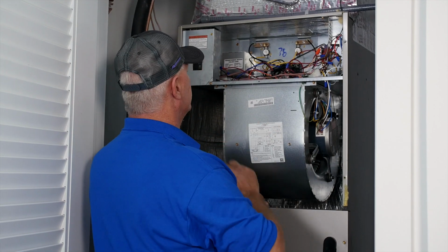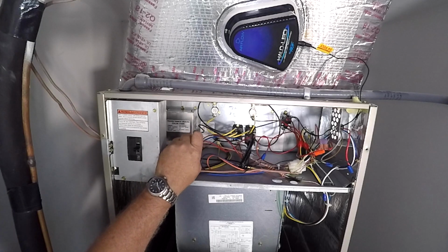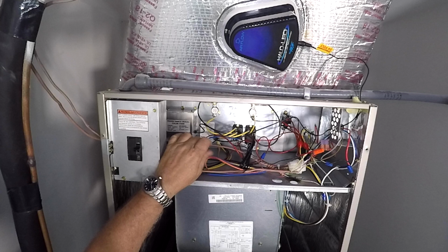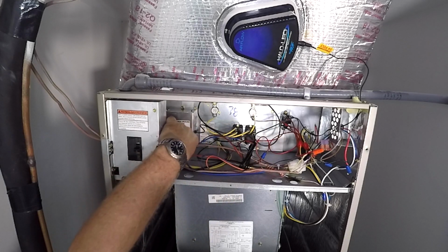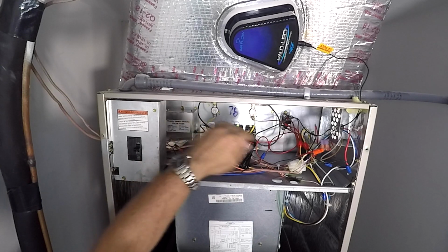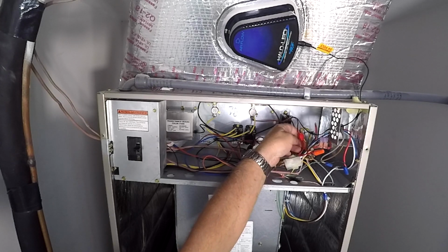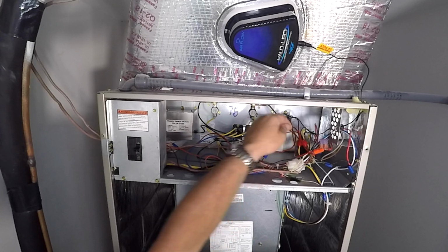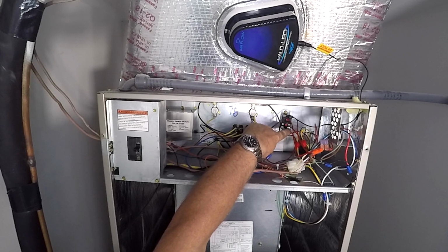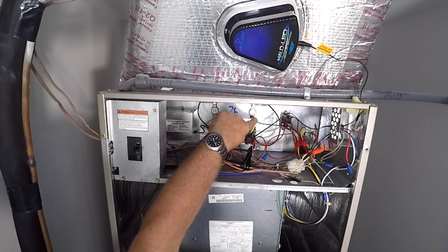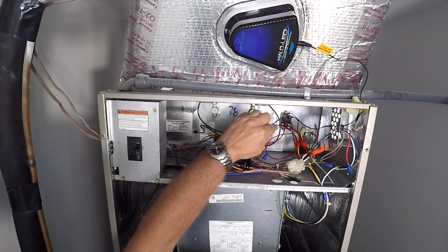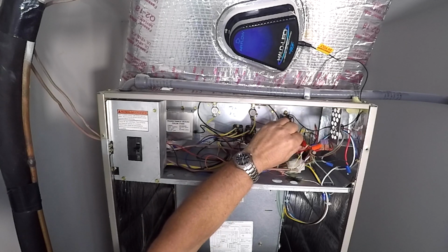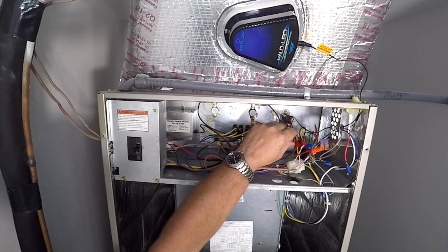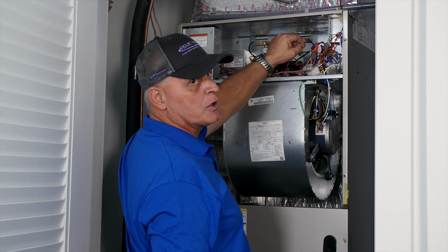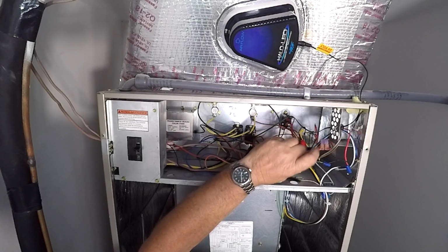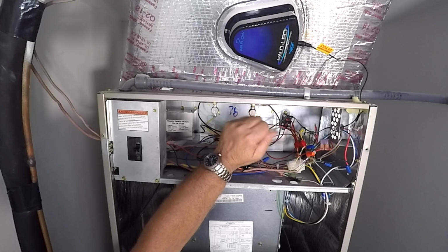Okay, so now to cover what we've done for wiring, we've wired our transformer to be controlled by the relay. The output of the transformer connects to terminal 4 on the relay. Our line voltage on the other leg comes into the relay from our common, or in this particular instance, we use the black wire, which is the common for the 240 volts. Our yellow wire on this one is what we're using to feed our relay on terminal 2 from line voltage. And then we have coming off of the heat sequencer relay, or terminator in some units, we power into terminal 5. Our low voltage, we have yellow connected to terminal 1, which is going to energize the relay anytime the unit is in a call for cooling. Our common connected to the brown, as it's common for that particular usage.